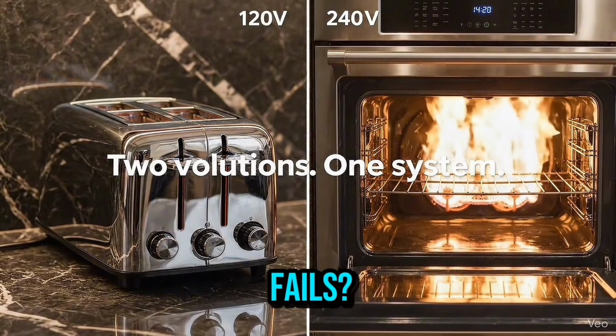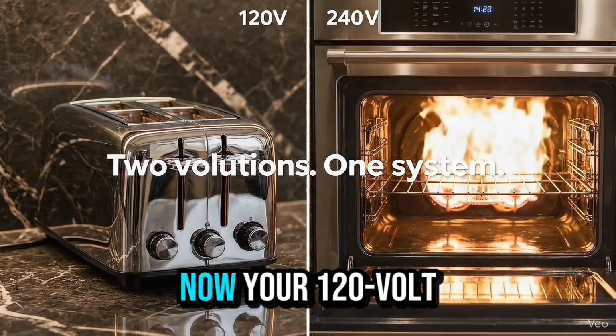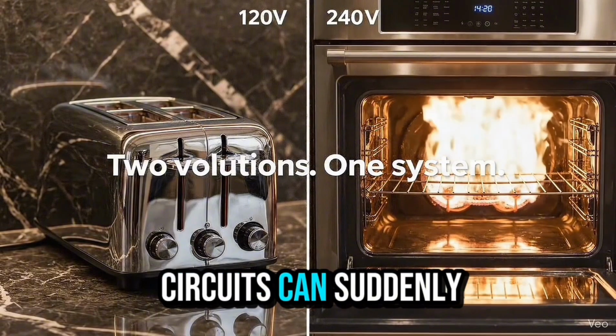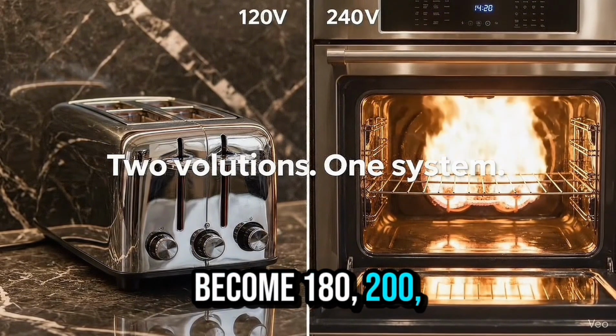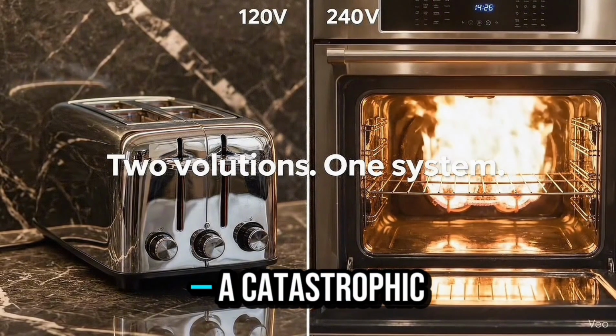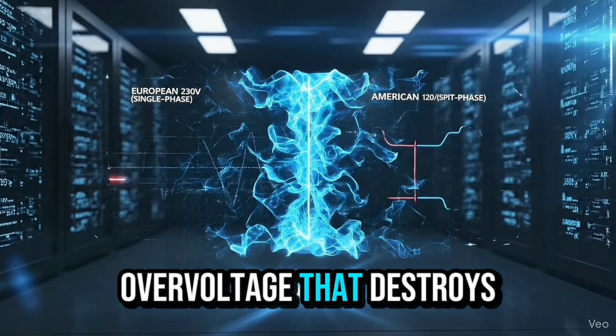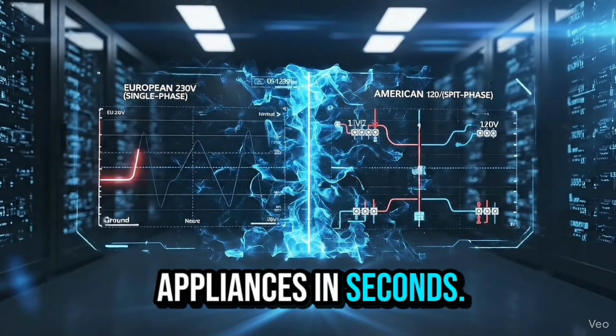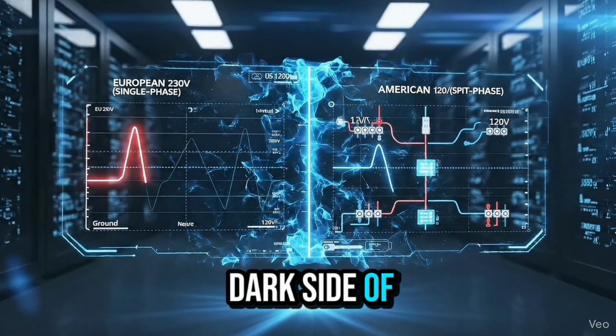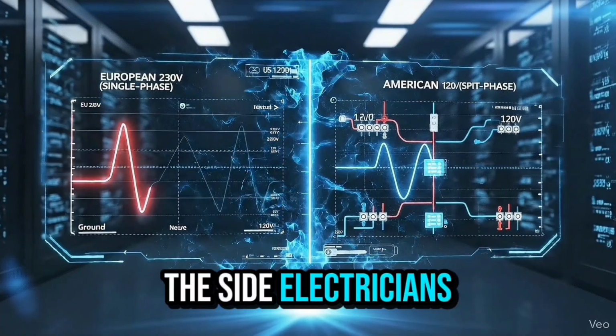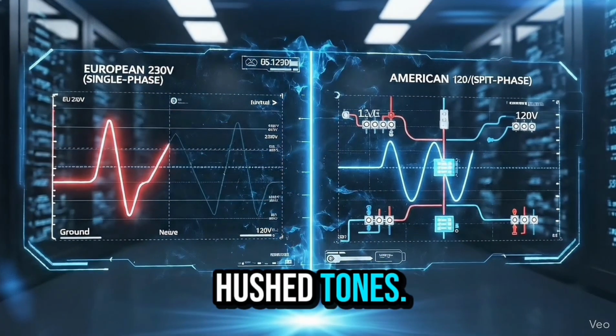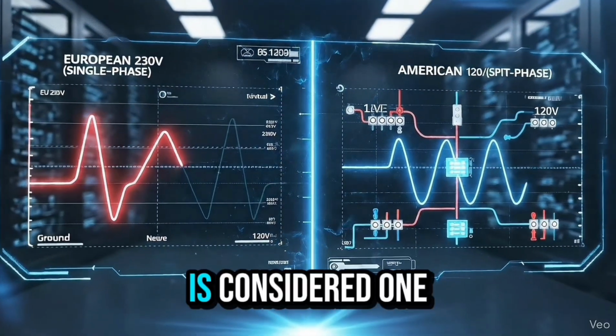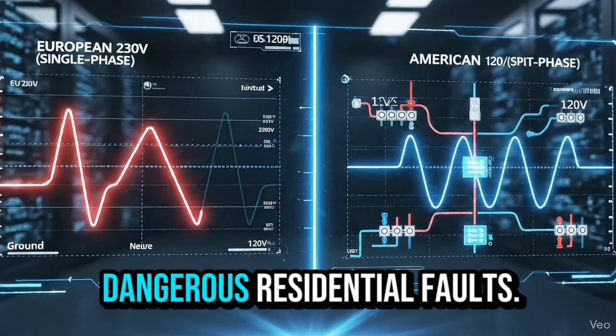If the neutral fails, then all bets are off. Now your 120-volt circuits can suddenly become 180, 200, even 240 volts, a catastrophic overvoltage that destroys appliances in seconds. This is the dark side of the American electrical system, the side electricians talk about in hushed tones, the reason an open neutral is considered one of the most dangerous residential faults.